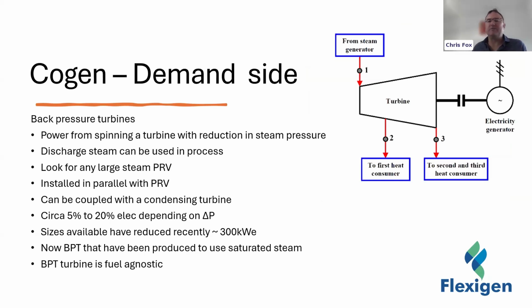A back pressure turbine isn't very different from the steam turbines that make power in a coal-fired or nuclear power station. It basically runs by taking high pressure, often superheated, steam, pulling it through a turbine, and taking it out at a lower pressure. The difference between what's done at a power station and a back pressure turbine is that at a power station, they take the discharge steam pressure pretty much all the way down to vacuum.